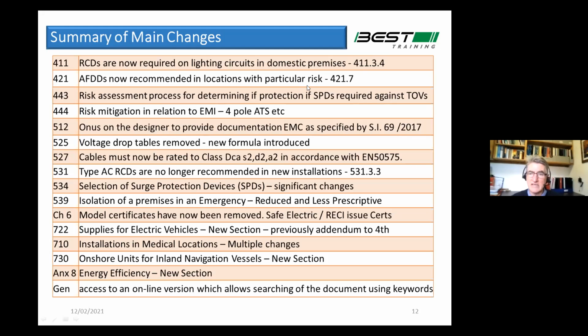That's not clear, but it definitely is required in places, or recommended, in nursing homes and communal buildings and the like. And that's really open for discussion. It's really not 100% clear what way people are responding to that. There's now a risk assessment process for determining if surge protection devices are required. My own view is don't bother doing it, just put in the SPDs. It's the right thing to do. And if you don't put in SPDs, you've got to demonstrate now that you've carried out a risk assessment to show that they're not required.